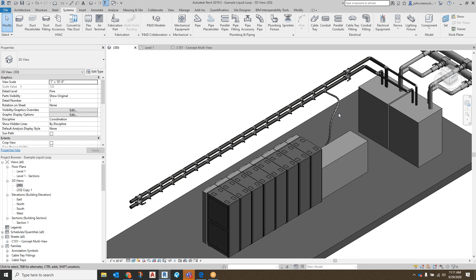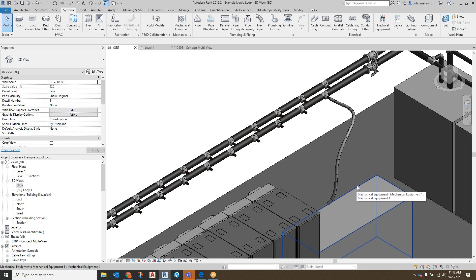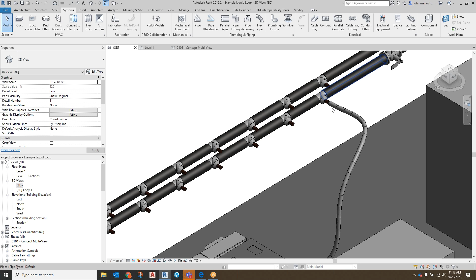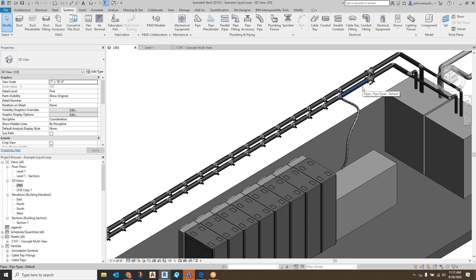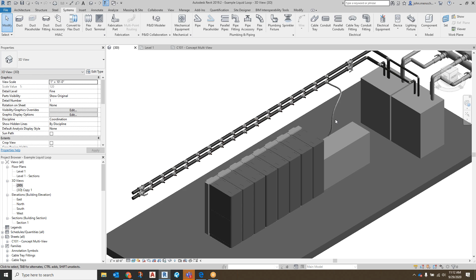Like Vali mentioned, it could be chilled water, a condenser loop, or something else, as long as it's appropriate. Then how do you deal with redundancy? Here's another example - this is a bad design, by the way, I cut this out from something else. There were other units over here, but having a supply and return that's not designed as a reverse return or Tichelmann loop means this would have a lot less pressure over here than the units up here. So I'd say recommendations on pressure equalization probably should be included.